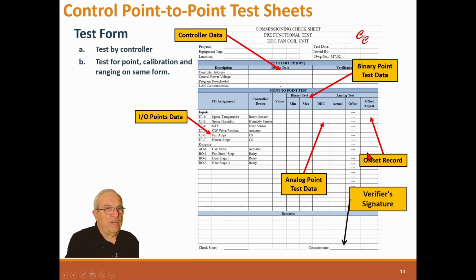So here we record the actual offsets, and what needs to be recorded in this form becomes a part of the report. But one piece of information that needs to get to the operators is what offset we actually put in the controller. And this is something that needs to become obvious in your report. And the reason is because if this controller fails and they replace it, the offset goes out the window with it. So they need to know what offset they had to put back in, or recalibrate the sensor anyway. That'd be a better way to do that.